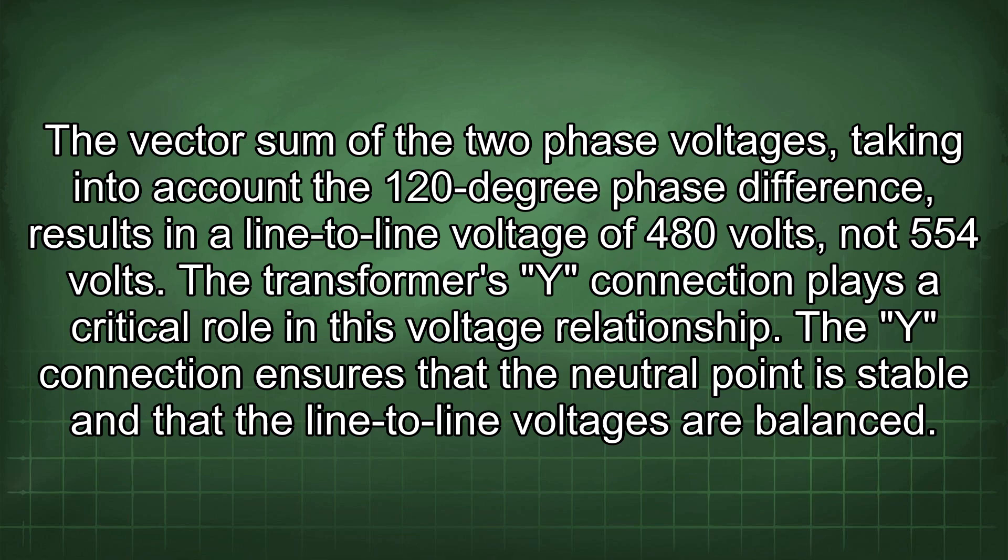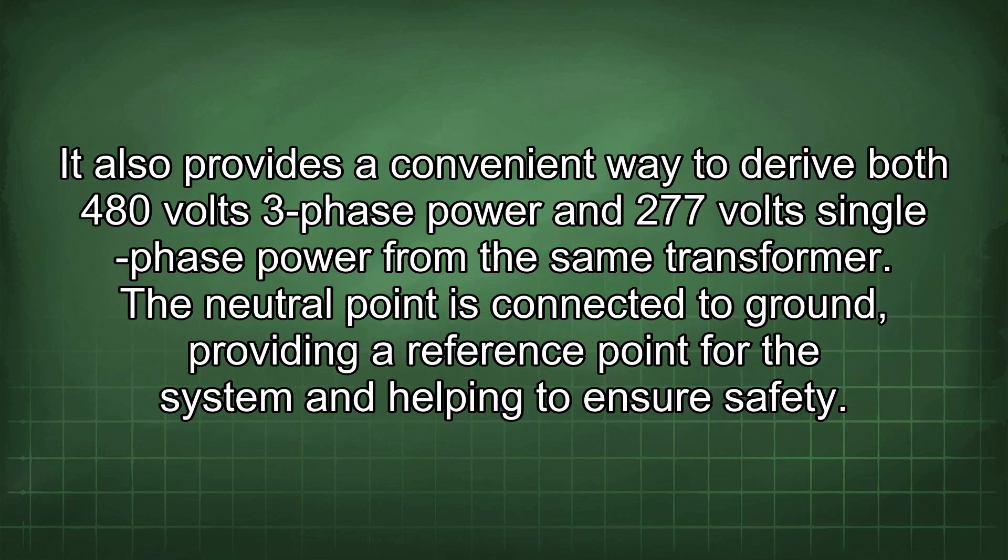The transformer's Y connection plays a critical role in this voltage relationship. The Y connection ensures that the neutral point is stable and that the line-to-line voltages are balanced. It also provides a convenient way to derive both 480 volts 3-phase power and 277 volts single-phase power from the same transformer. The neutral point is connected to ground, providing a reference point for the system and helping to ensure safety.